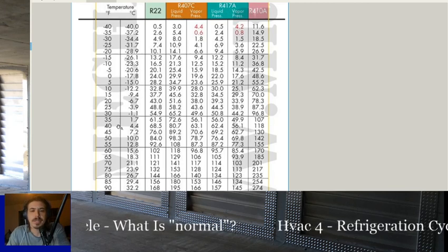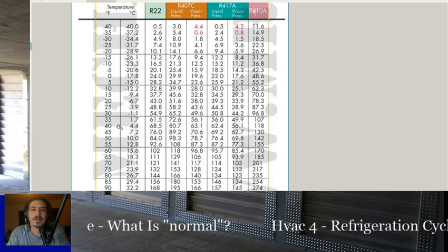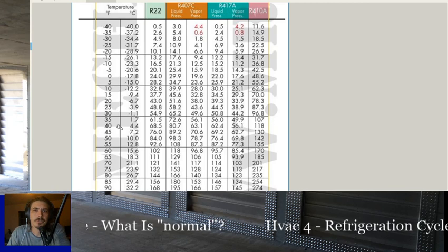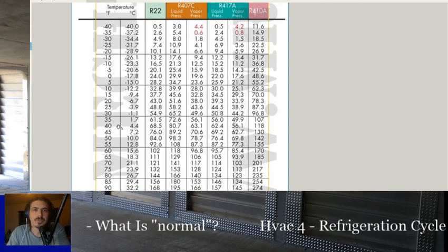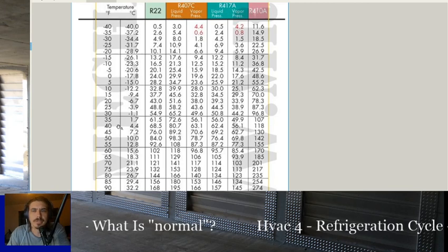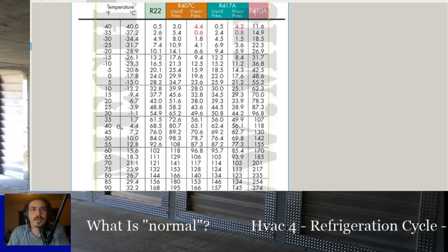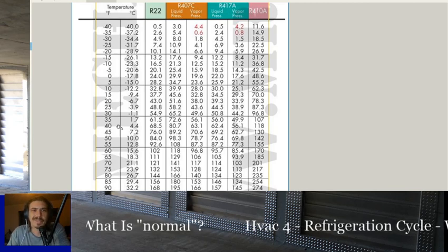So generally, instead of saying, oh, my suction line pressure should be, I'll try and say, my saturated temperature of my refrigerant should be. And that's going to help you a lot when you're switching refrigerants. As we get new refrigerants down the road, you'll understand, okay, this is what I'm looking for as far as temps. Because if I don't have these temps, then everything else doesn't work.